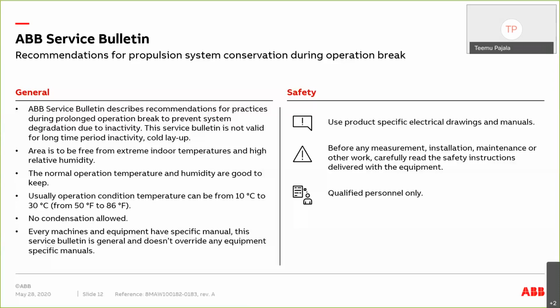The most important things in all layup conditions are temperature and humidity, mainly from the electrical equipment point of view, which is what we are considering here, since it's ABB's core product, and then some other details for the Azipod, which turns more to the mechanical side. Basically, the two major things that kill the electronics are high temperature and high humidity, and those two things need to be taken care of. Of course, corrosion on the mechanical side, like shafts, needs to be considered, but that's not as critical as it is for the electronic boards. From a safety point of view, always refer to product-specific electrical drawings and manuals. That should be the source of information.